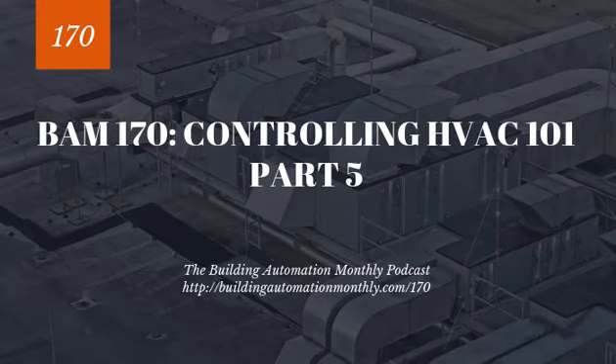That and balancing valves. I recall I was troubleshooting a central plant. This is back in Texas for a church, and churches are massive in Texas. I think this church had like 20,000, 30,000 people. And it had 3 centrifugal chillers and a smaller centrifugal chiller. And it had a decoupler. And we were trying to figure out why the secondary loop was just out of control. And what it ended up being, we went into the central utility plant, and you could hear that one of the pumps was deadheading. Someone had bumped one of the multi-purpose valves. That's a valve that serves as a strainer, as a balancing valve, etc. And what happened is they bumped it and partially closed it, and that actually was constricting the flow coming out of one of the secondary pumps.